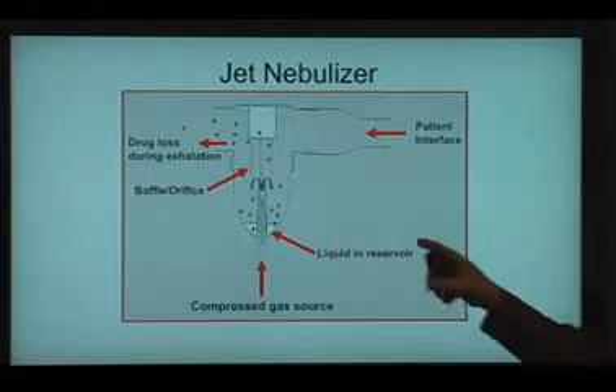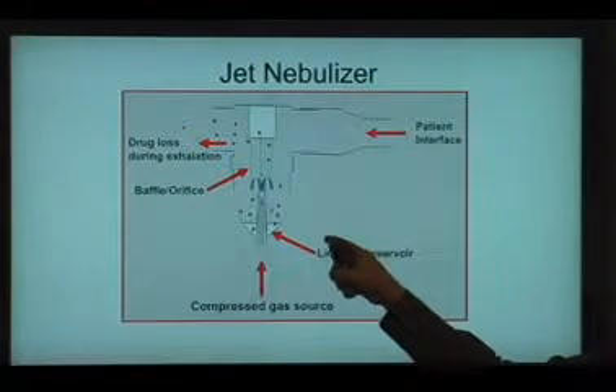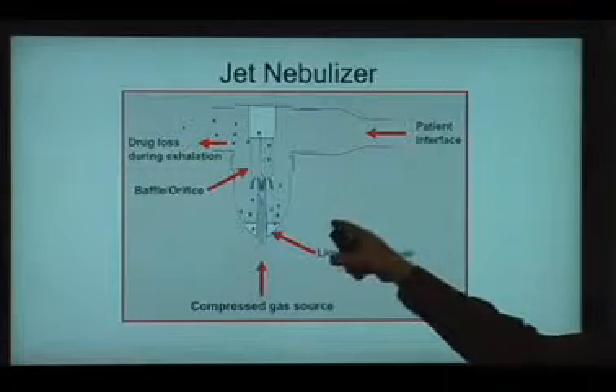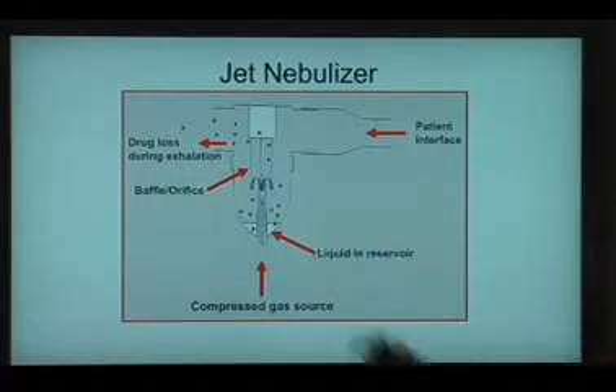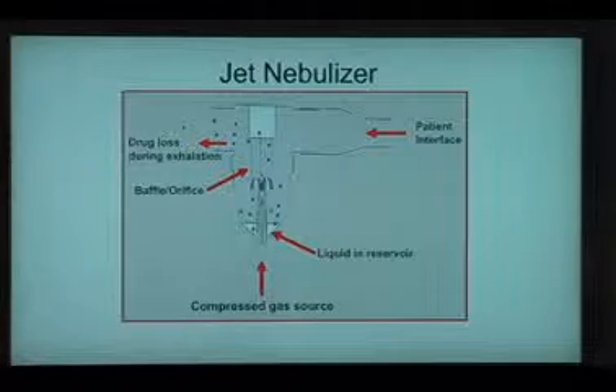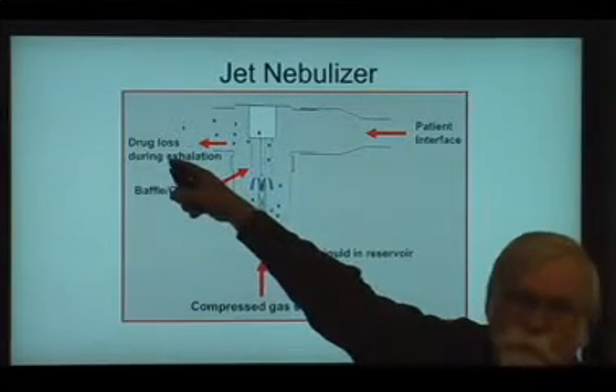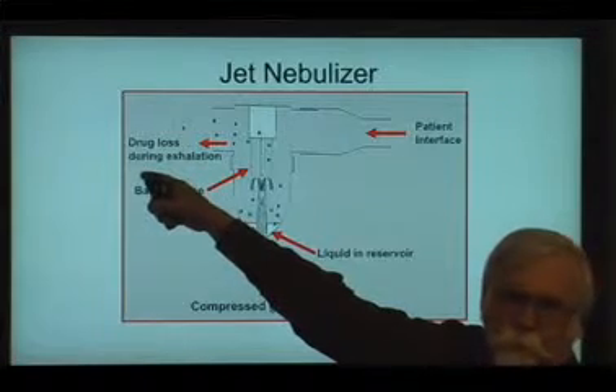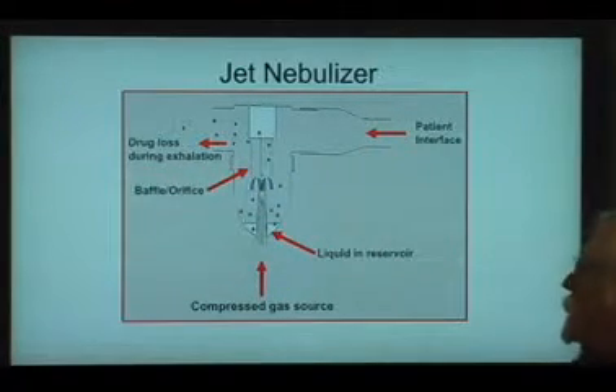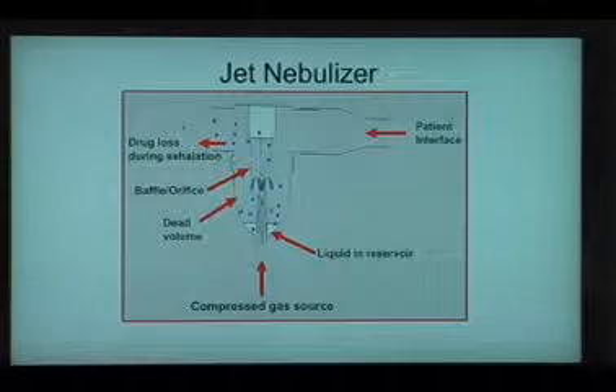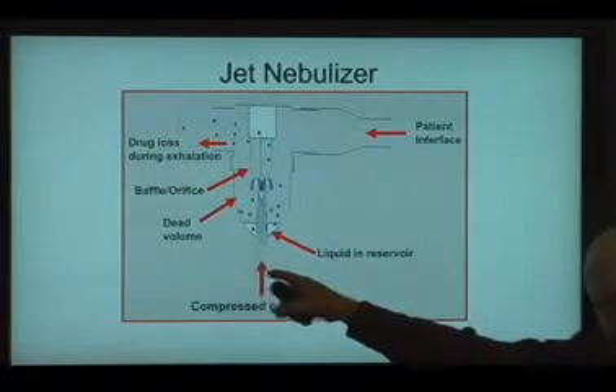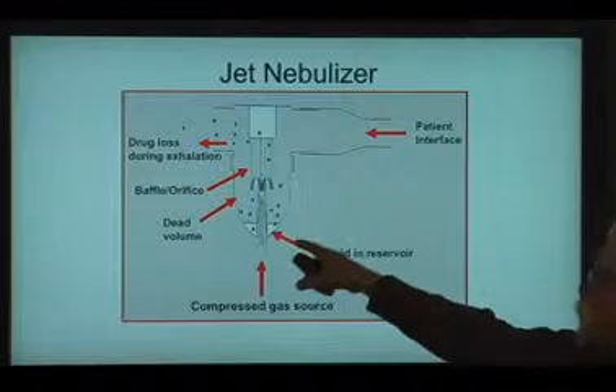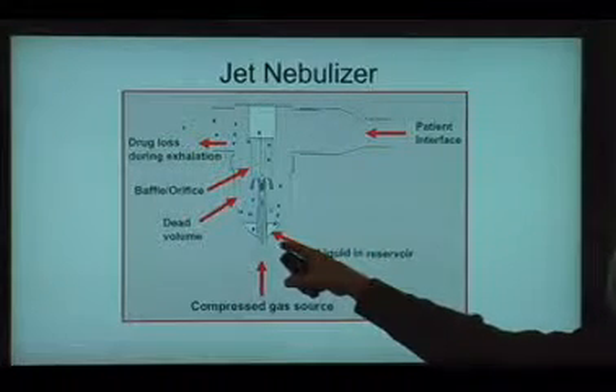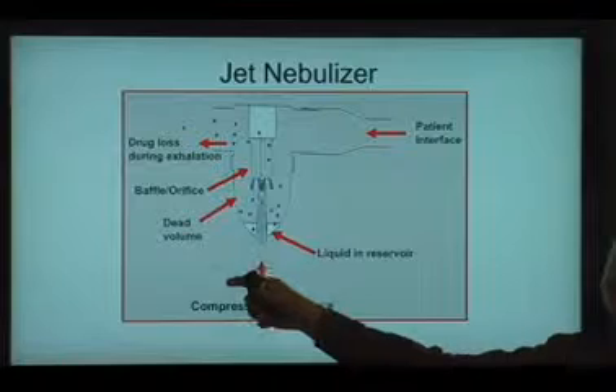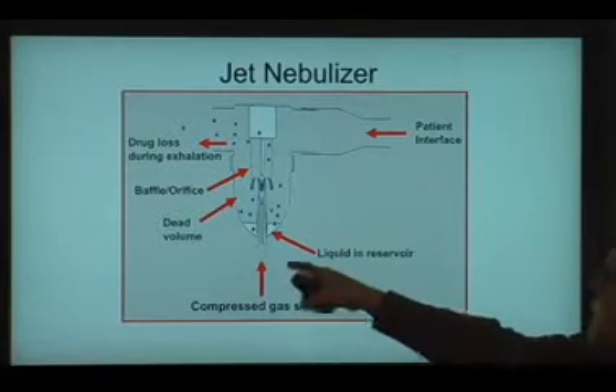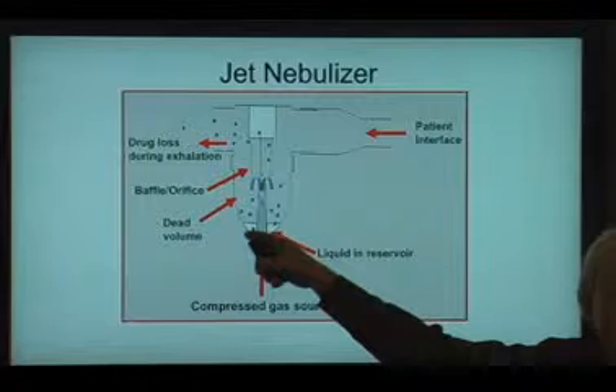And because the expiratory phase is much longer than the inspiratory phase, the nebulizer tends to be a very inefficient aerosol delivery device. There's probably more aerosol that gets blown into the face of the caregiver, you and me, than is actually inhaled by the patient. Moreover, with a jet nebulizer, there is a certain dead volume, which is the volume of solution which remains in the nebulizer cup after the nebulizer stops producing an aerosol. And that dead volume is typically about a milliliter.